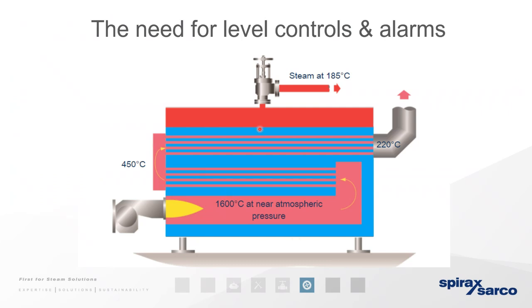And the chamber where the tubes turn 180 degrees can be surrounded by water exposed to the shell. So effectively that means it's either a dry back or a wet back. In this particular case, you've got a dry back. I think that's right, is it? Yeah, which allows for your pass tubes. In this example, we describe a boiler with 3 passes. So we're going to be talking about a 3-pass boiler here and a wet back. Sorry, that's a wet back.